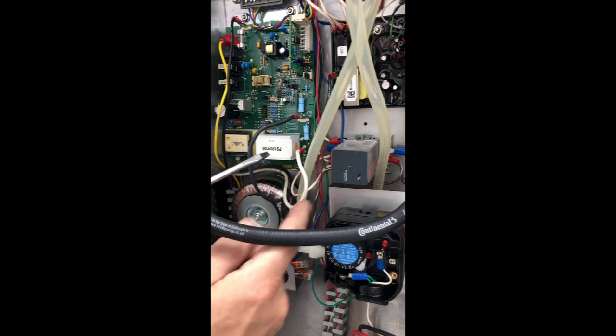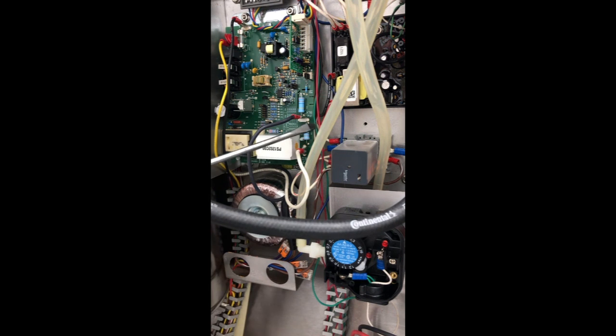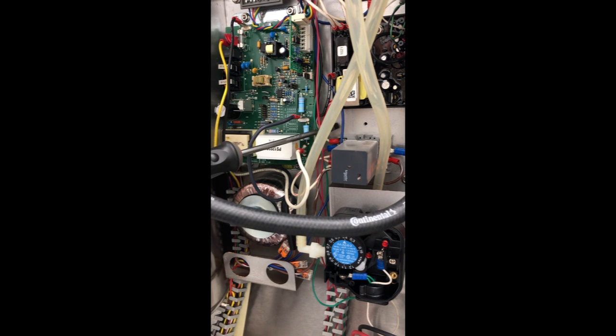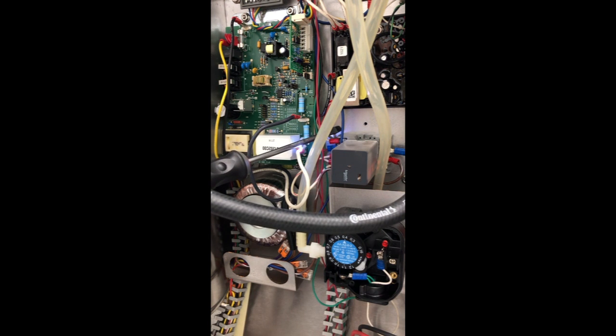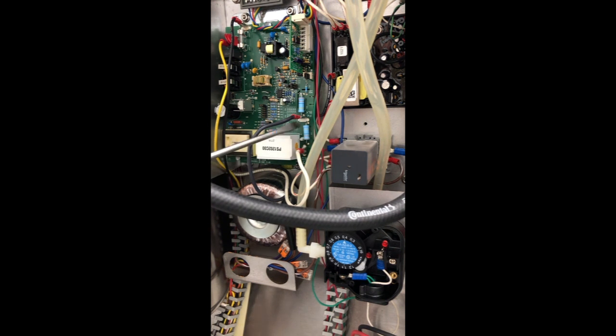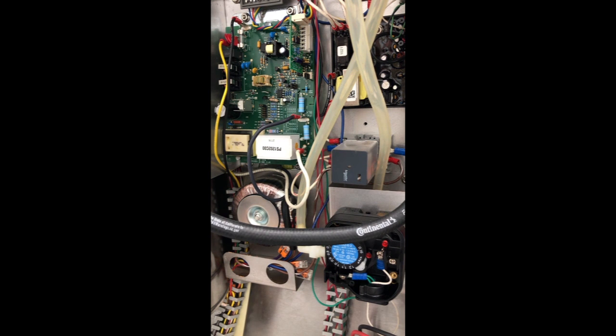And then when worse comes to worse, if you really want to test your output, you can take a screwdriver, make sure that it's well insulated, ground the tip of it, and when you pull it in next to P3, that wire jumping like that. You see that power jump? P3? That tells you that you're getting the high voltage output. By the way, this white wire coming from P3 is the one that should be going to those wires. So that's a real good way of testing that. If you see that this fuse up here is blown for whatever reason, go ahead and get rid of the board. There's no sense in replacing the fuse. The board has done all it's going to do, and it's gone.